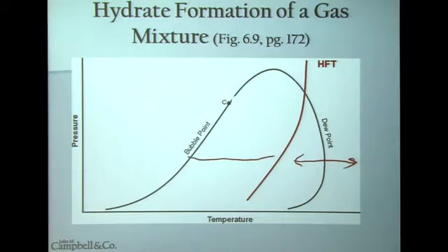However, if your system temperature is colder than the hydrate formation temperature, and if you have free water in your system, you run the danger of forming hydrates.